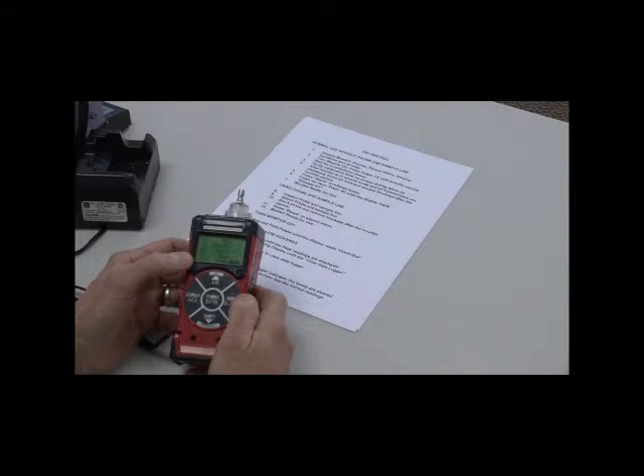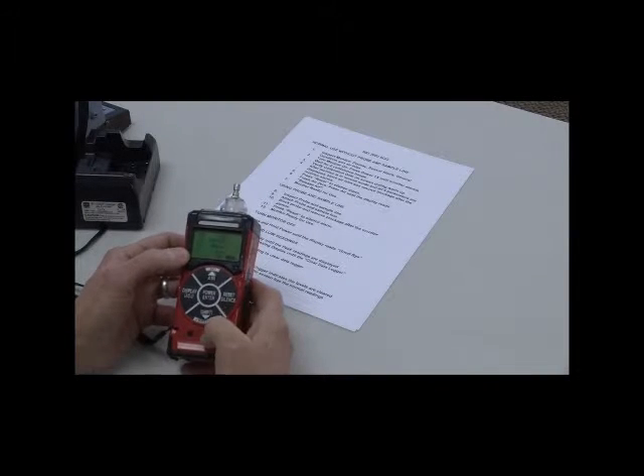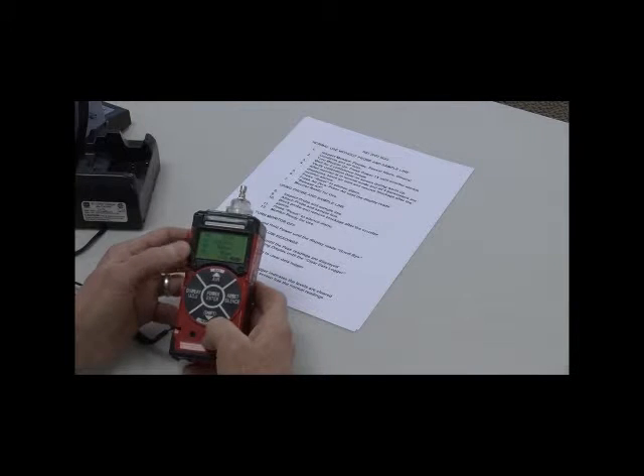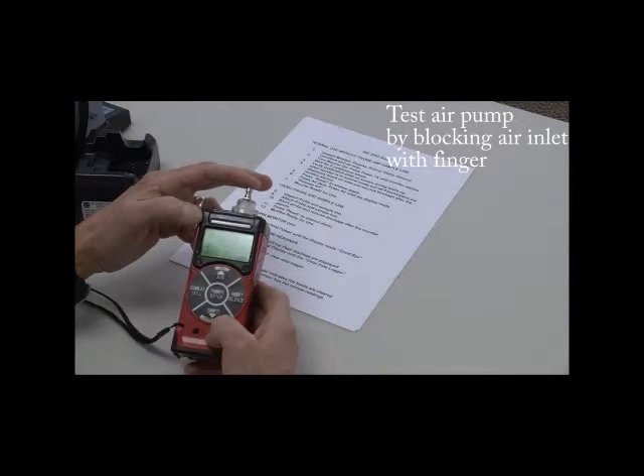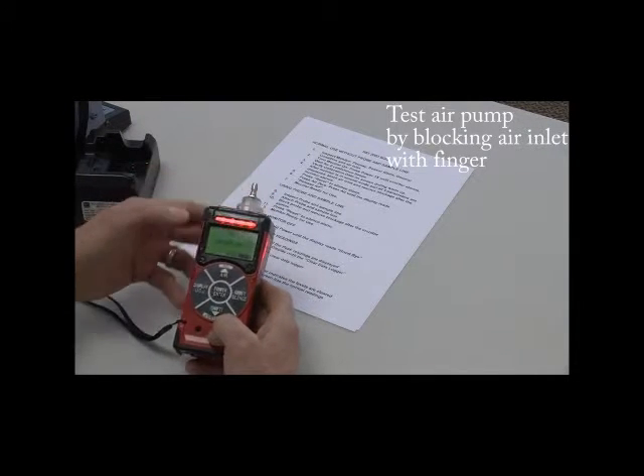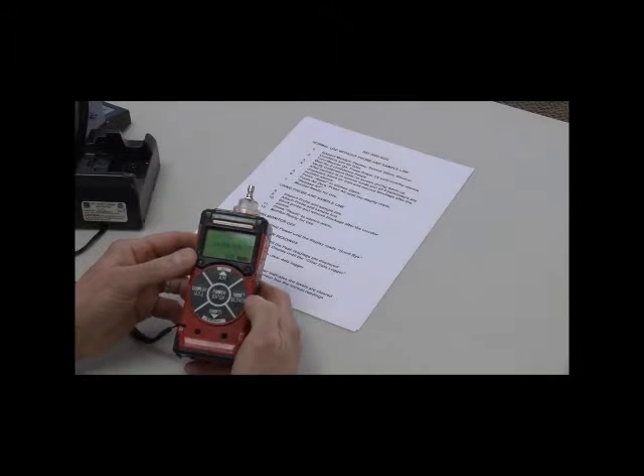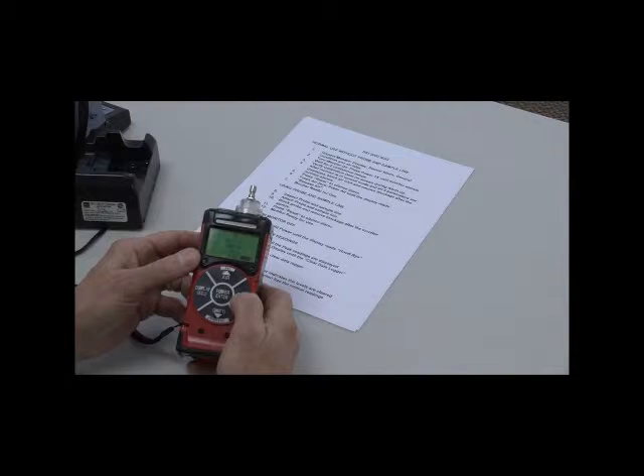At this time, I need to test the air inlet to make sure that it is pulling air in through the filter properly. I'm going to block the sample. It's going to alarm to let me know that I've had a failure. To fix it, I'm going to press the silence reset button.